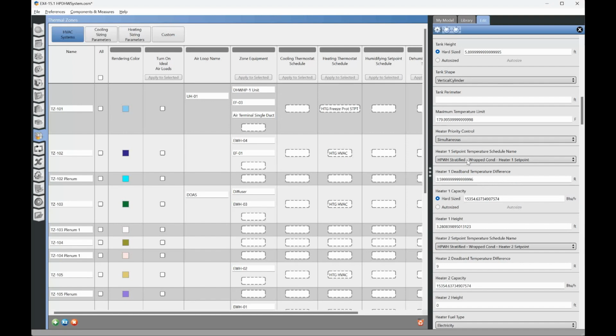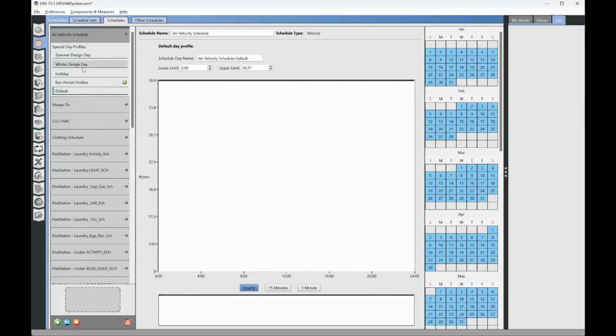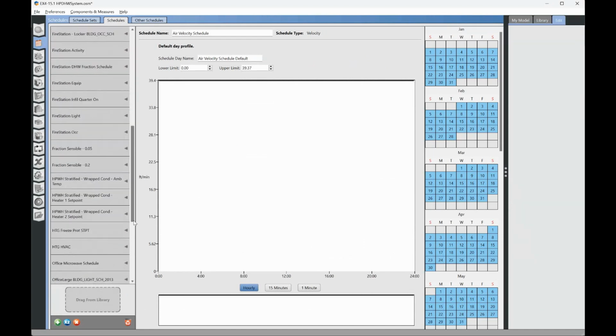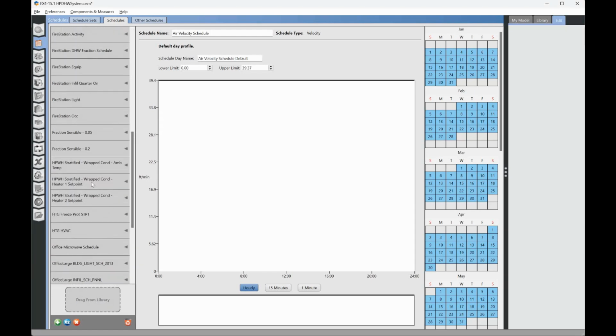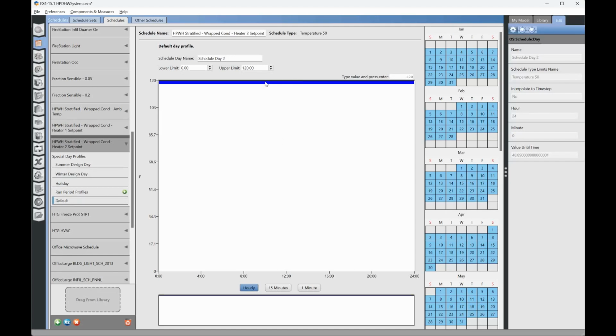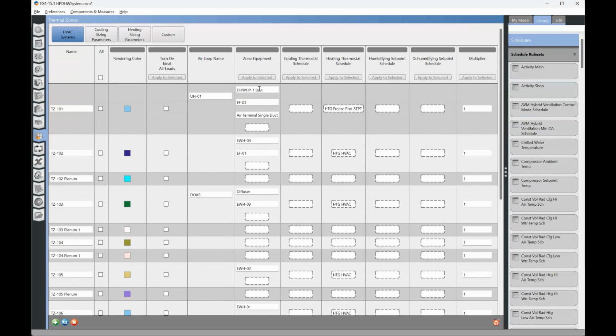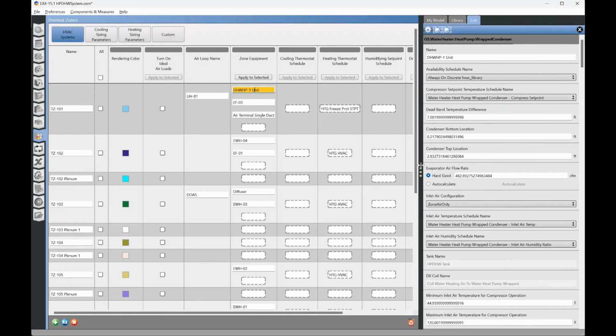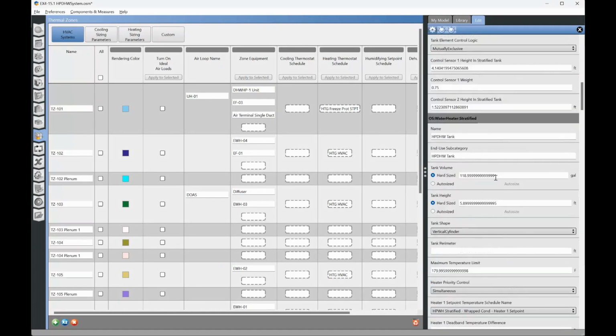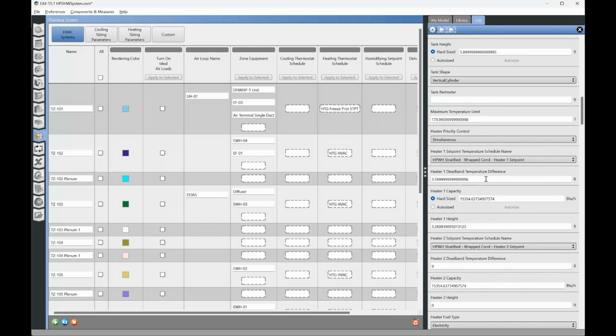And in this case, it is this set point, and we can take a look at the schedule. And if we go to schedules, heater 1 set point is 120, heater 2 set point is also 120. So it's going to try to maintain that 120 degrees. And it's going to have a dead band. So if it starts dropping below 120, it drops and drops and drops. And once it gets down to about 3.6 degrees down, about 117, 116, that's when the heaters are going to kick on.